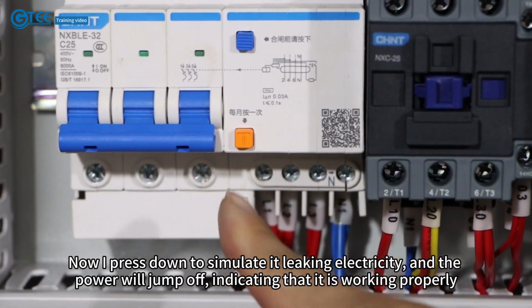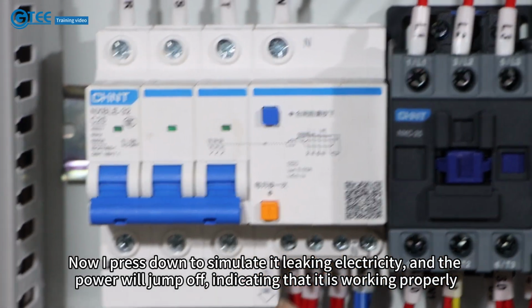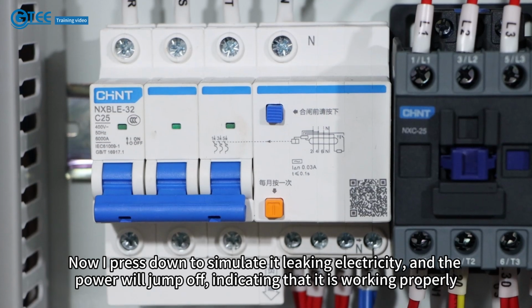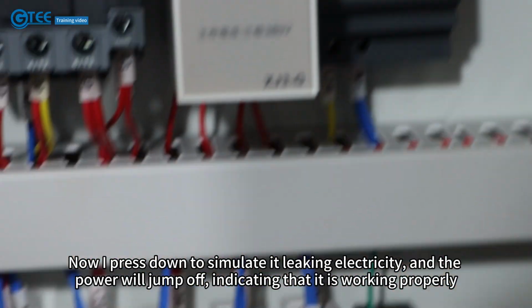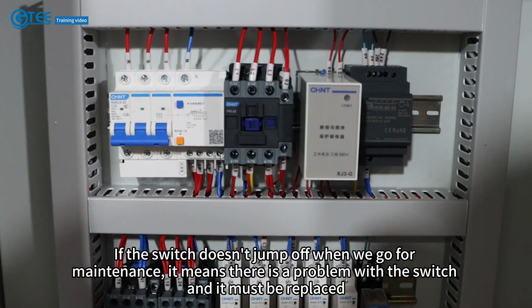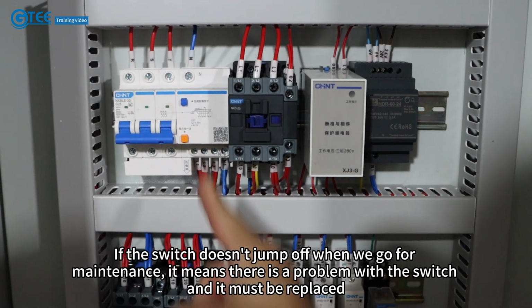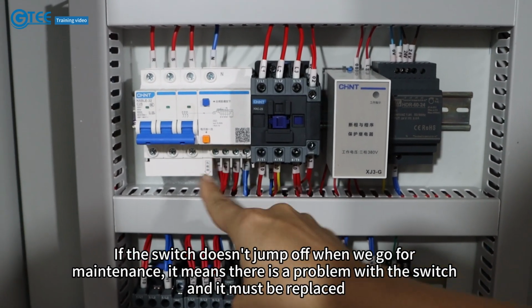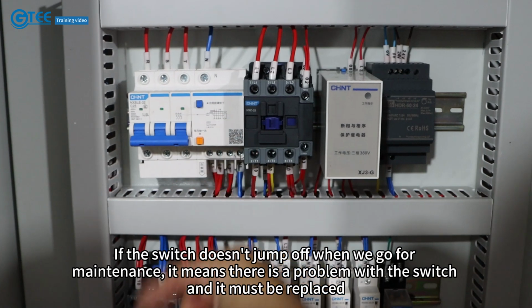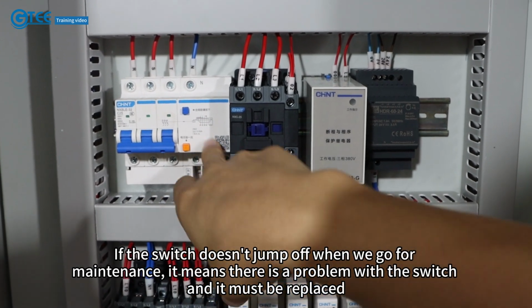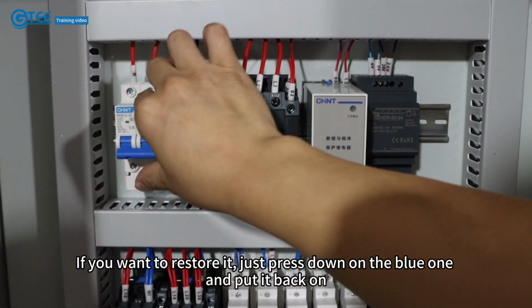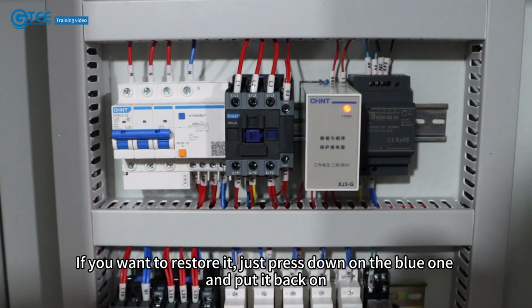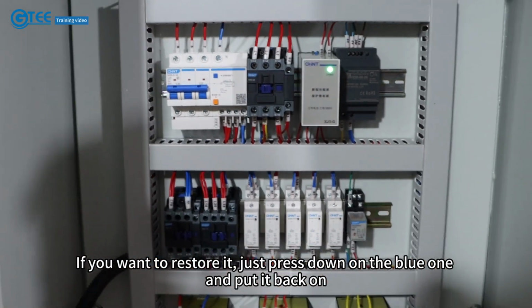Now I press down to simulate it leaking electricity, and the power will jump off, indicating that it is working properly. If the switch doesn't jump off when we go for maintenance, it means there is a problem with the switch and it must be replaced. If you want to restore it, just press down on the blue one and put it back on.